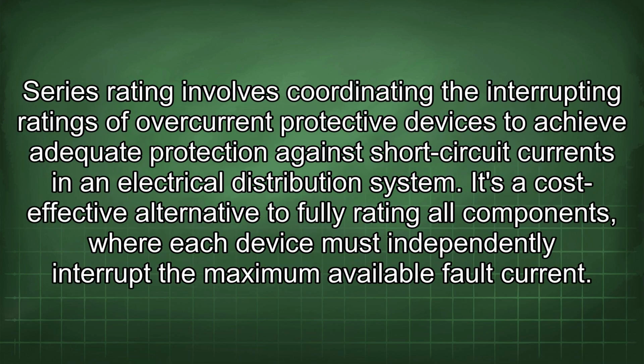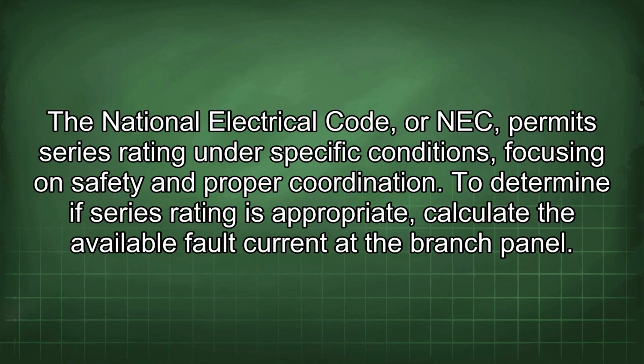Series rating involves coordinating the interrupting ratings of overcurrent protective devices to achieve adequate protection against short-circuit currents in an electrical distribution system. It's a cost-effective alternative to fully rating all components, where each device must independently interrupt the maximum available fault current. The National Electrical Code, or NEC, permits series rating under specific conditions, focusing on safety and proper coordination.